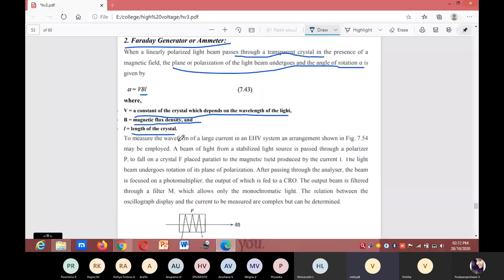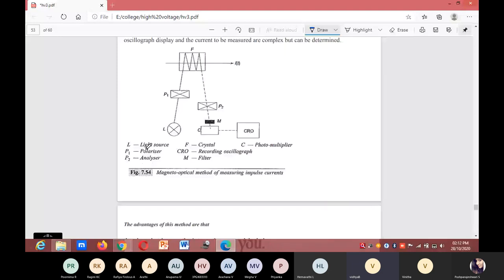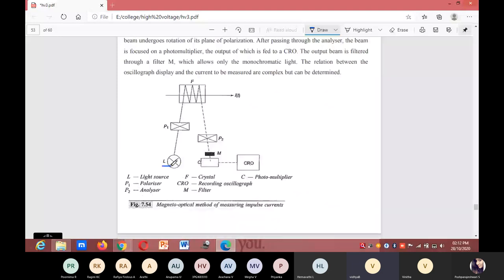To measure the waveform of a large current in an extra high voltage system, an arrangement is used where L is the light source, P1 is a polarizer, P2 is an analyzer, F is a crystal, CRO is a recording oscilloscope, M is a filter, and C is a photomultiplier.